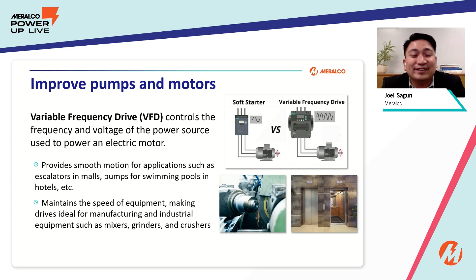Another thing to consider is the use of variable frequency drive, or VFD, for your motors and pumps. VFD saves energy by reducing power when not required and regulating motor speed. It has advanced overload protection, keeping motor starting currents low and reducing thermal and mechanical stresses on motors and belts during starts, lessening wear and tear.